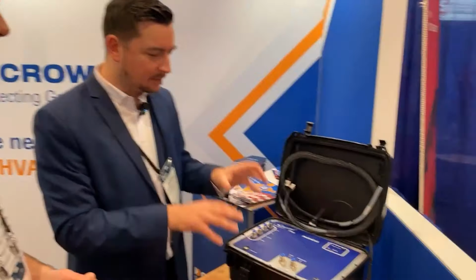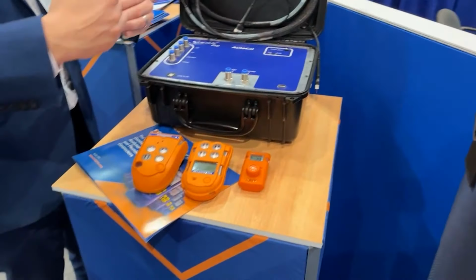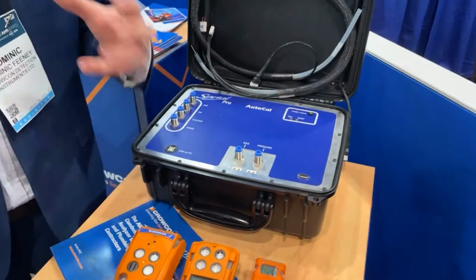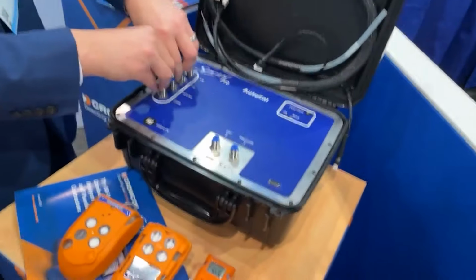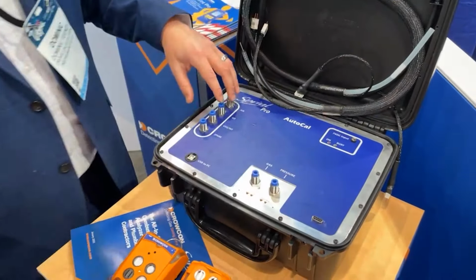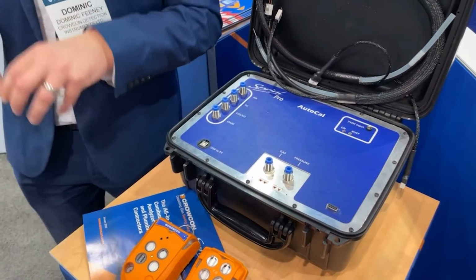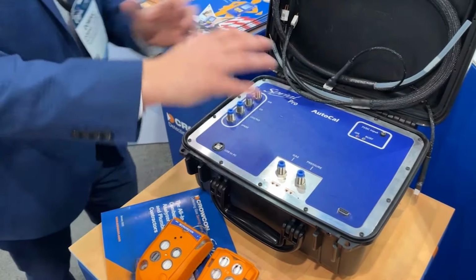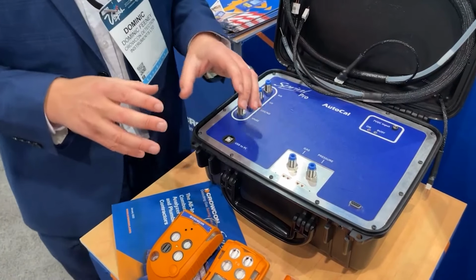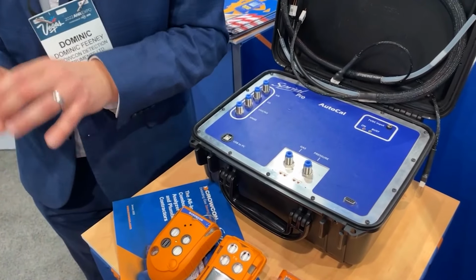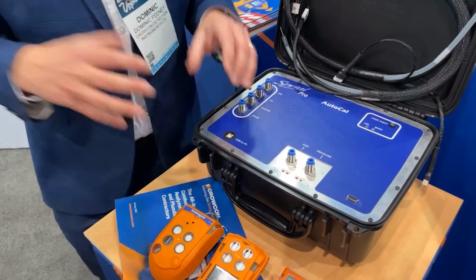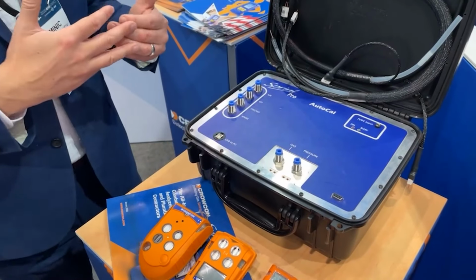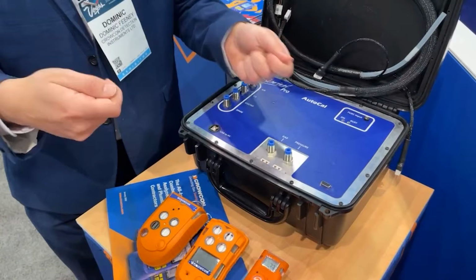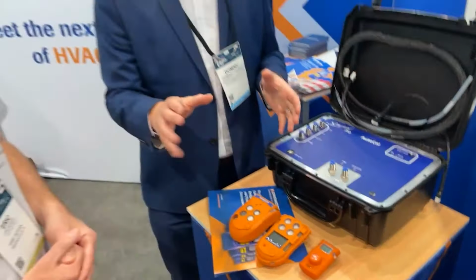We've developed something we call the auto cal jig. This is a really clever bit of engineering that automates the process and makes it much more streamlined and quicker. Your gas is connected to it, your device is connected via this umbilical, and you connect it to a PC which drives the process. At the click of a button, it runs in a fully automated fashion, taking about five to seven minutes depending on how many sensors the device has. It takes minimal interaction from the engineer performing the process, and at the end you see if you've passed or failed. If you've passed, happy days, off you go. If you've failed, it might need a sensor swap, and then you do it again.